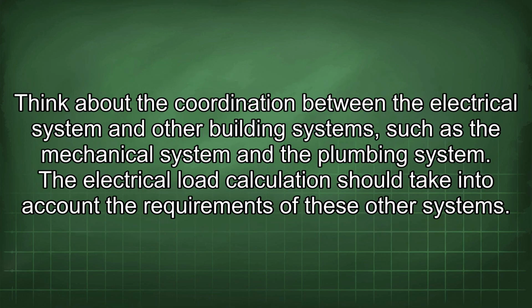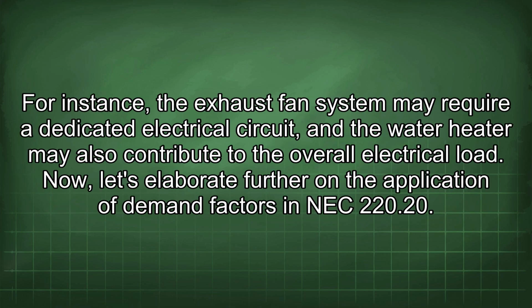Think about the coordination between the electrical system and other building systems, such as the mechanical system and the plumbing system. The electrical load calculation should take into account the requirements of these other systems. For instance, the exhaust fan system may require a dedicated electrical circuit, and the water heater may also contribute to the overall electrical load. Now, let's elaborate further on the application of demand factors in NEC 220.20.